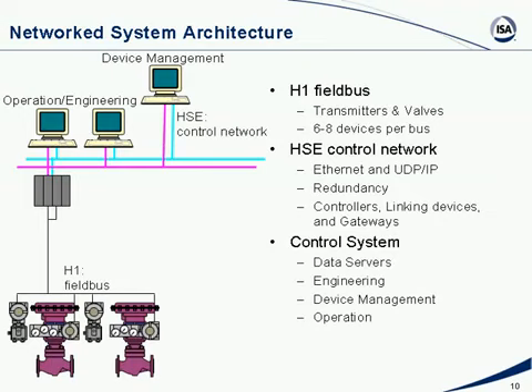There are some other good features also in Foundation Field Bus. For example, automatic addressing, so you don't need to set addresses using dip switches. It's all completely automatic, so it eliminates human error. And obviously with hundreds or thousands of devices in the plant, it's good that this is automatic, plug and play, so to speak. Foundation Field Bus also allows peer-to-peer communication, okay? So a transmitter can publish a value directly to a valve positioner, so you can even do control in the field. We'll talk more about that.